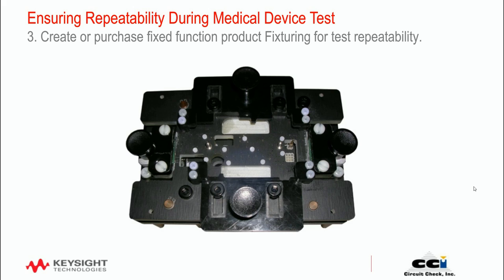The PCBA was attached to the fixture, typically in a conducted or wired RF coexistence test environment on the benchtop. Probes make contact to the underside of the PCBA using a wireless test fixture plate. Then standard off-the-shelf cables connect from the back bottom side of that fixture over to a spectrum analyzer, an oscilloscope, a DMM, and so on. What's missing in this picture is a view of the connector from the bottom side.